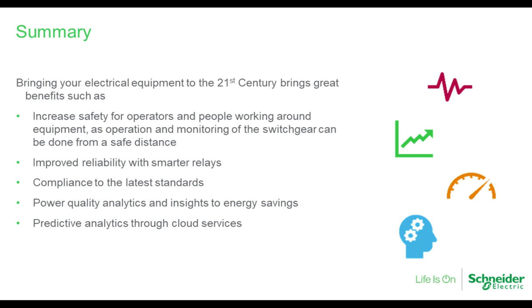Predictive analysis through cloud services. Again, there are services such as Schneider provides that can look at all of this information and all this data that's being collected now by these devices and help determine what's going on in the system, whether it could be a transformer that's failing, could be a breaker failing, it could be bus failing. We need to look at all of the information provided to get a better, clear picture of what's happening in that system. And again, with older equipment, you can't gather that information because it's not available to you. And you just have to sometimes go on hope and testing and maintenance and hope that gets you through and that you can catch some of these items before they fail.